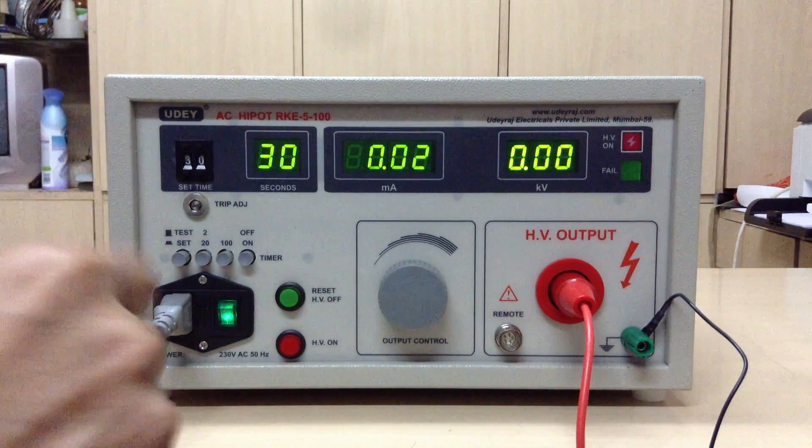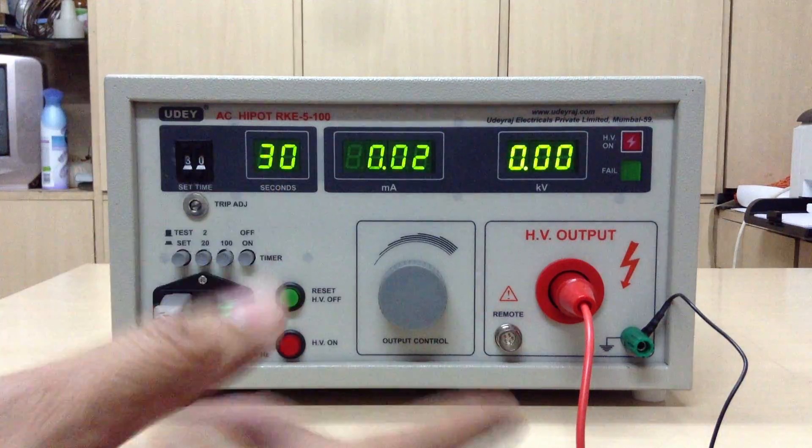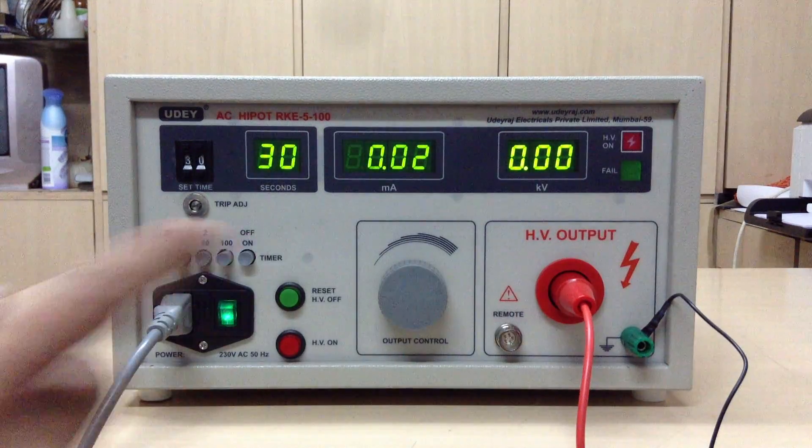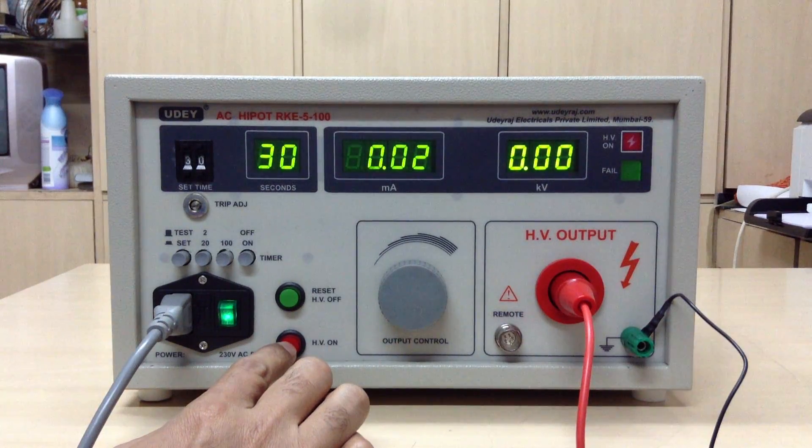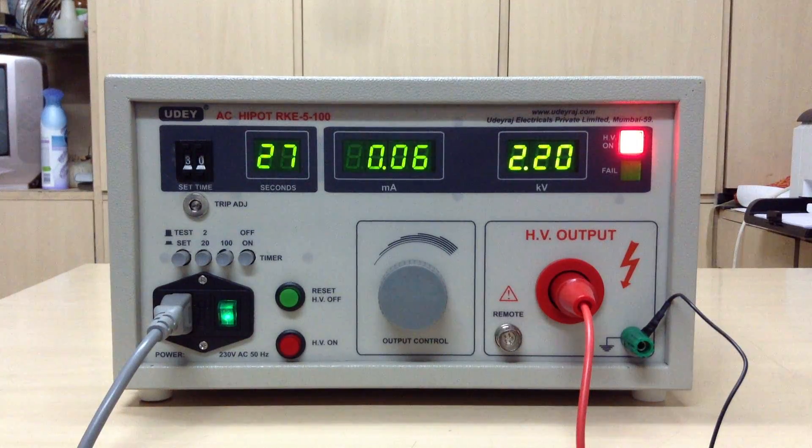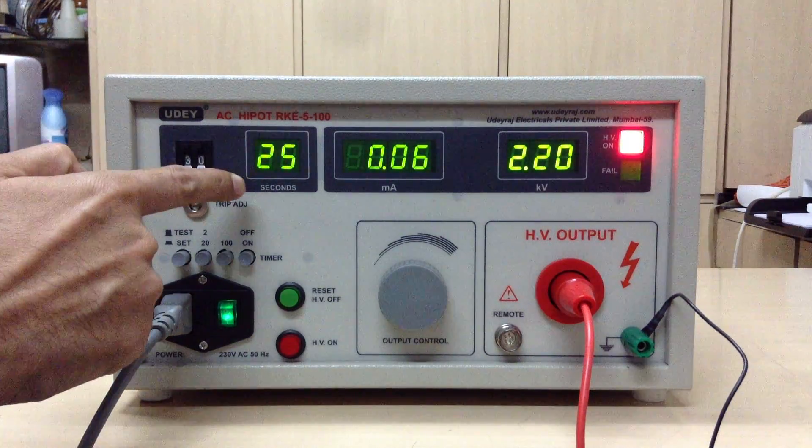On test mode now you can connect the object or item under test with the HV and the earthing lead, and then just need to press the HV ON. It will automatically go to 2.2 kV which was selected by us and the timer gets ON.